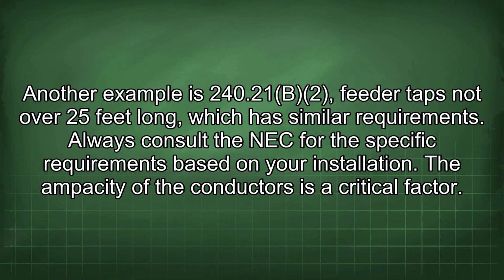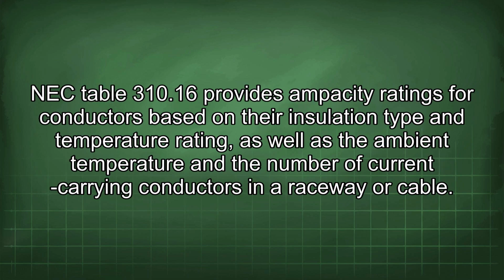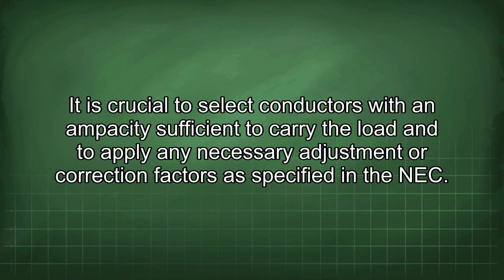The ampacity of the conductors is a critical factor. NEC Table 310.16 provides ampacity ratings for conductors based on their insulation type and temperature rating, as well as the ambient temperature and the number of current-carrying conductors in a raceway or cable. It is crucial to select conductors with an ampacity sufficient to carry the load and to apply any necessary adjustment or correction factors as specified in the NEC.